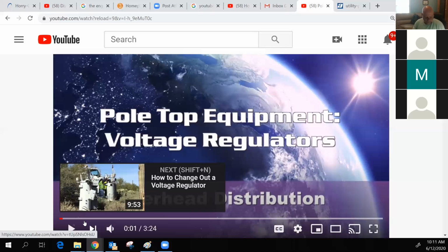It works in conjunction with other equipment. Sometimes engineers figure it to work with capacitor banks, which we'd have at the end of the line too. If a thunderstorm came through and a fuse blew on the capacitor bank, we'd have to go check that as well. But the voltage regulator was the main piece of equipment we dealt with to make sure voltage stayed at its proper level.